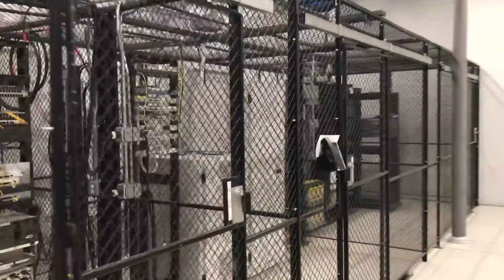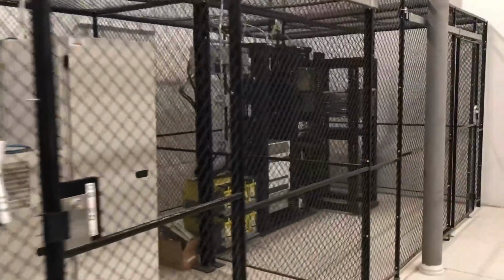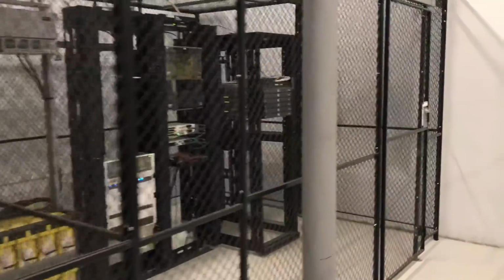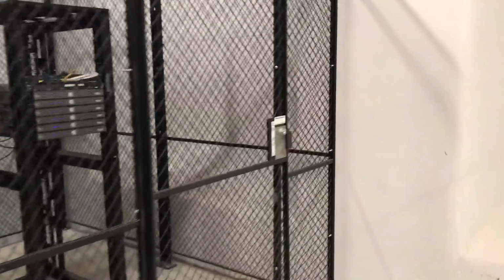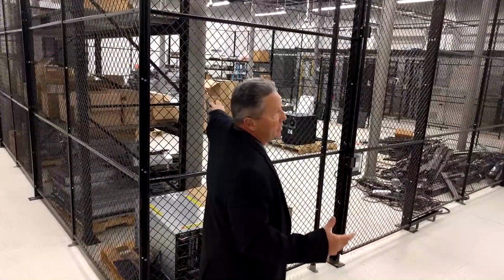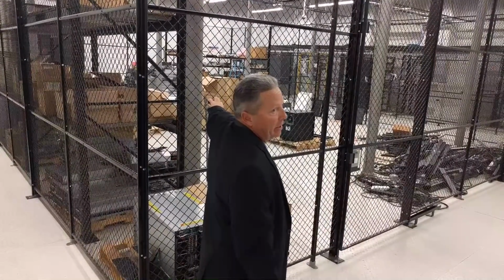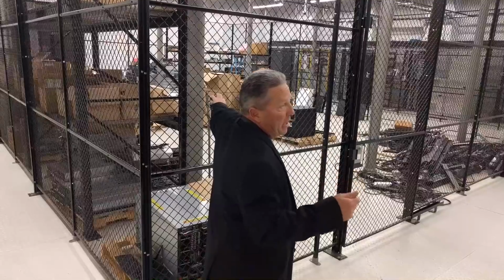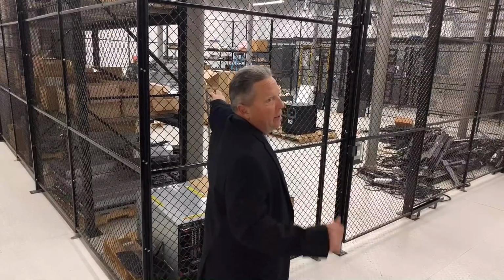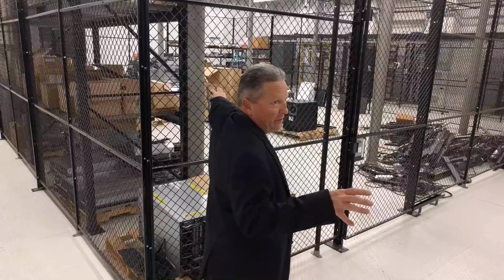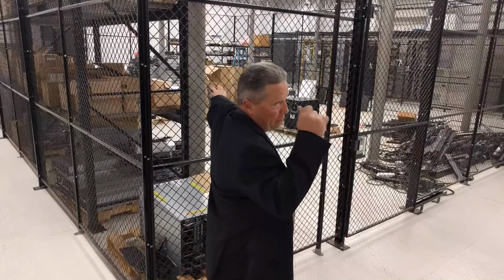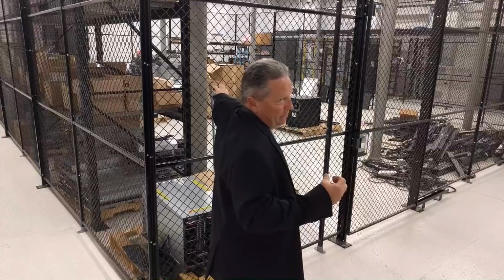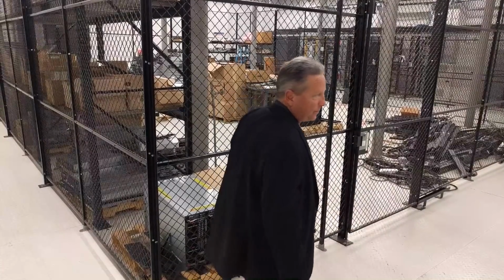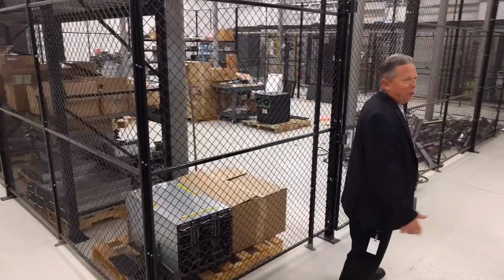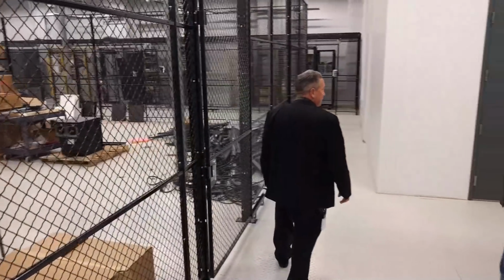So all 201,000 square feet of the building is obviously sprinklered, some of it in 3 different levels. You'll have it in the basement, above the drop ceiling, and below the drop ceiling. But in the case of this building, this entire pipe is dry, it's got nothing but air in it. So if you were to trip a head, trip a smoke, or trip a heat sensor, all we would do is fill the sprinkler pipe. You literally have to burn a head off to get water out of it. But the entire pipe is dry. It's a little safer, gives us an extra 30 seconds before the water comes at you.